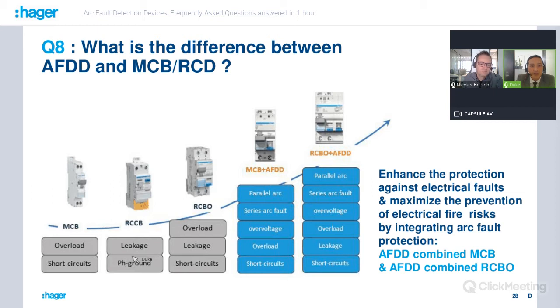Now imagine that we combine the MCB plus the AFDD functions in one device, and an RCBO plus the AFDD functions in one device. We will increase the level of protection. We maximize the prevention of electrical fire risk with a complete set of fault types. We go to a better level of protection, and we try to maximize that. We enhance the protection of our electrical system.